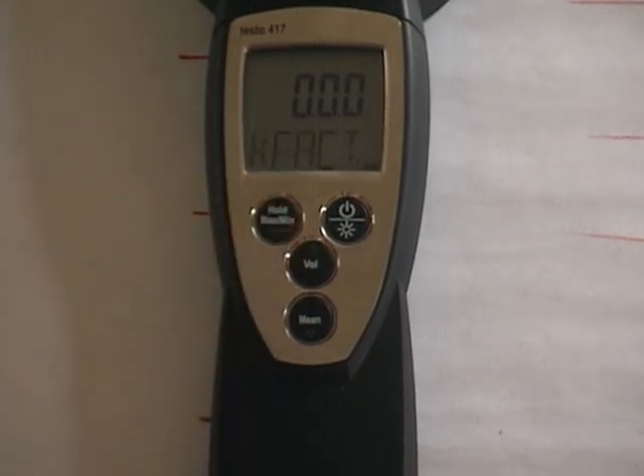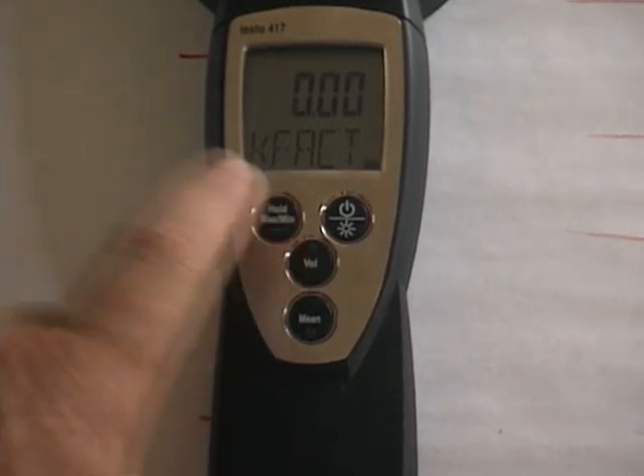We toggle to the next, K Fact. That is the area factor for the return grill. So if you have a return grill that only has 50% open area, you would set the K Fact at 0.5 for 50% open area.